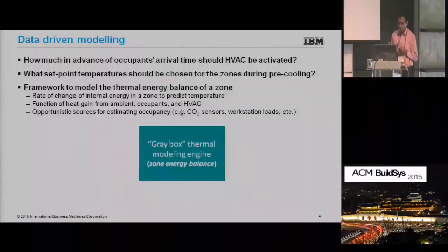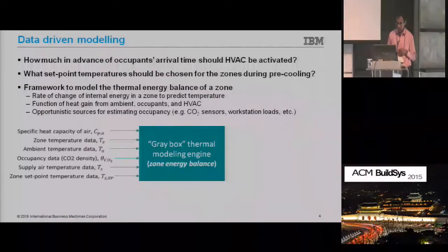What we build is what we call a gray box thermal model for zone level information. It takes in parameters from the building management system, as shown on the left: zone temperature data, airflow temperature, occupancy information, and so on. We also feed in the control algorithm for the VAV boxes, to avoid dependency on mass flow rate sensors, which can be particularly expensive compared to CO2 or temperature sensors.